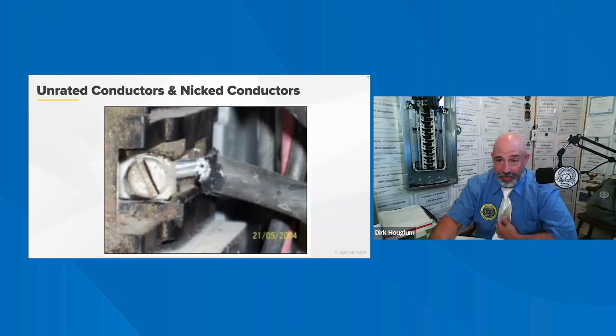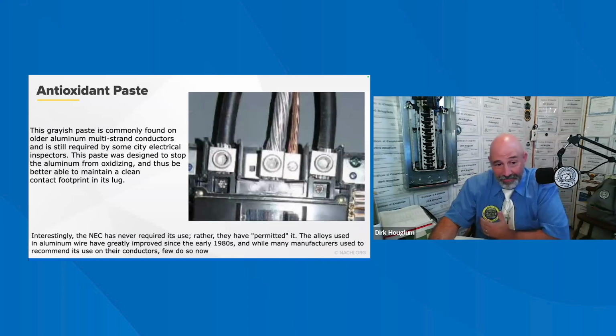The inspector should often see homeowner wiring with cut down extension cords as supply circuits. I think you guys can figure this one out on your own. Yeah, that's not good. You can definitely see that there is some galvanic corrosion there. The grayish paste is commonly found on a lot of aluminum, and just like the video was talking about earlier, that should be on a lot of the aluminum, unless it's the upgraded aluminum. You don't need that anymore. So when it's permitted, just keep an eye on stuff like that. You'll see it quite a bit.